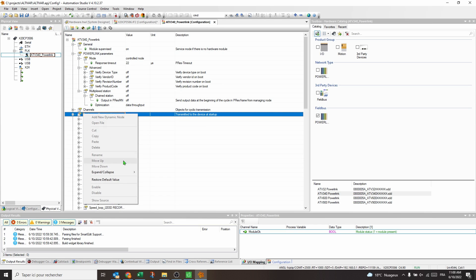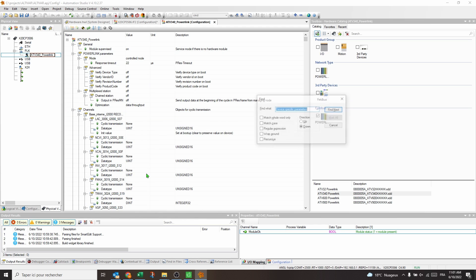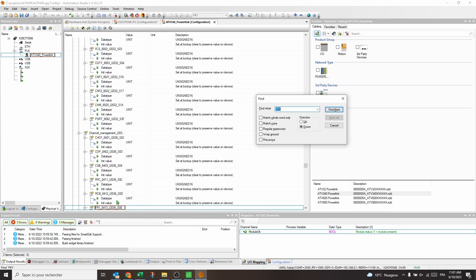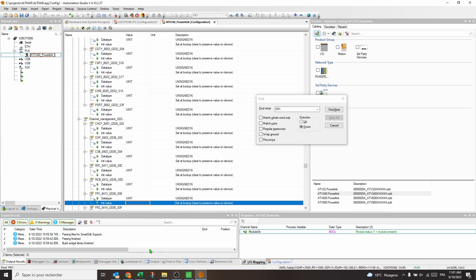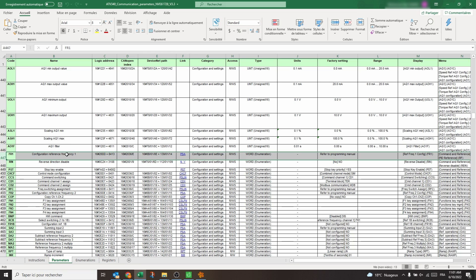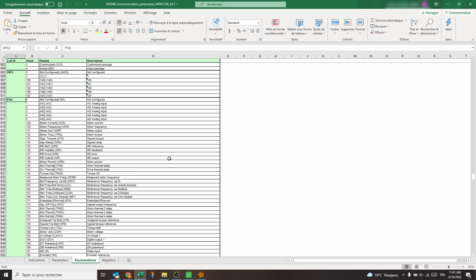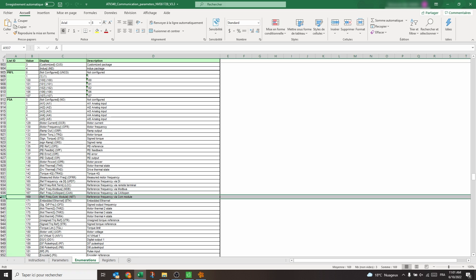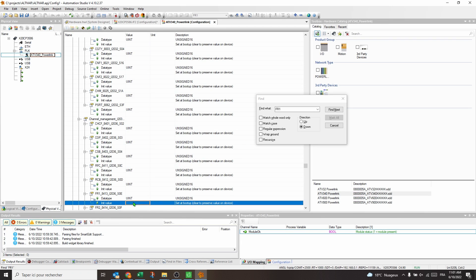Expand the device-specific parameters and search for parameter FR1. This parameter allows you to select the source of the command and the reference. In the ATV340 communication parameter file, downloadable from the Schneider site, the addresses of all drive parameters and their possible values are listed. To send the command and the reference via Powerlink, FR1 must be set to 169.